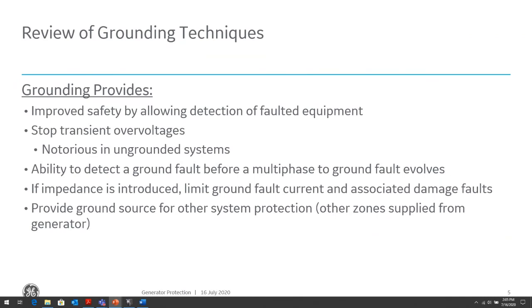Grounding provides us, number one, safety, by allowing detection of faults within the equipment. If there's a ground fault, there's a path for ground current to flow, so our relays can detect that ground fault current and isolate that faulted piece of equipment. It also allows us to stop or reduce transient overvoltages.